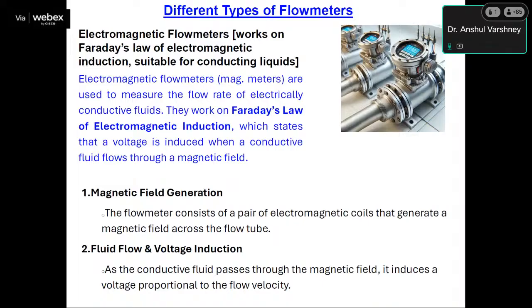The first example is the electromagnetic flow meter. It works on Faraday's law of electromagnetic induction, and it is suitable for conductive liquids only. We cannot use this flow meter for non-conductive fluid, because there will be no conduction and Faraday's law will not apply. Electromagnetic flow meters measure the flow rate of electrically conductive fluids. Faraday's law states that a voltage is induced when a conductive fluid flows through a magnetic field, and that voltage is directly proportional to the flow rate.